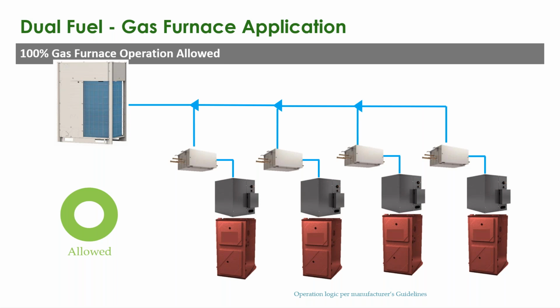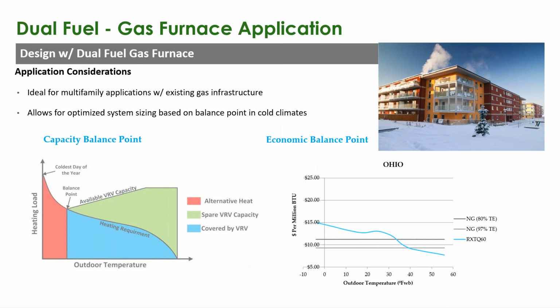Again, every manufacturer is going to have different logic for this, but all the manufacturers have some form of equipment to be able to operate in this fashion. Like I said, this is ideal for multifamily applications that already have a gas infrastructure or have a planned gas infrastructure, which most cold climates do. It allows you to optimize the system sizing based off of the balance point or the fuel cost in that area. In this example, you can see that they have a 5-ton. There's a couple balance points there, depending on the gas efficiency of the furnace: right around 39 degrees on the higher efficiency gas furnace and 34, 35 degrees on the lower efficiency gas furnace.